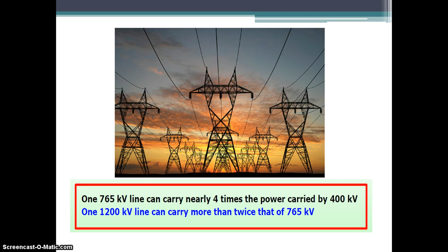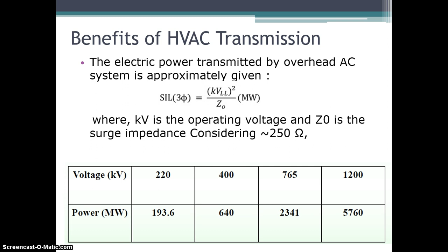Okay, and if you see at 765 kV, when the voltage level is doubled, the power delivery is approximately 4 times. So a 765 kV line can carry nearly 4 times the power carried by a 400 kV line. Okay, and one 1200 kV line can carry more than twice that of a 765 kV. तो यहाँ पे आप देख सकते हो कि 400 kV की लाइन अगर 640 मेगावाट ट्रांसफर करती है, तो अगर वोल्टेज लेवल डबल होता है, the power goes to 4 times. If voltage level is 3 times, means 1200 kV from 400 to 1200, then it is equal to 5760, यानी कि 9 times हो जाएगा power delivery.